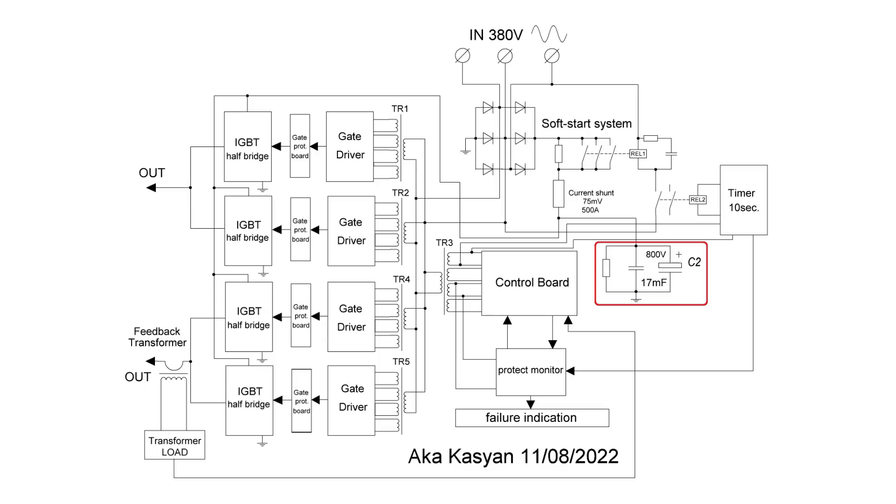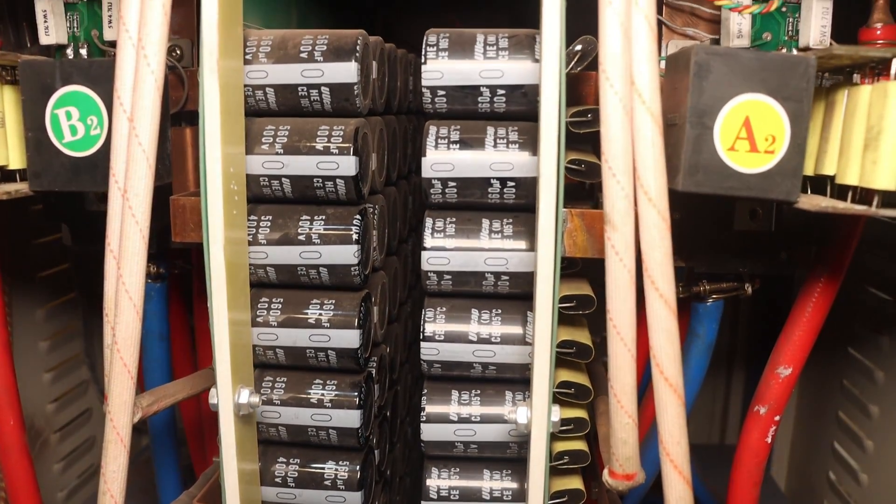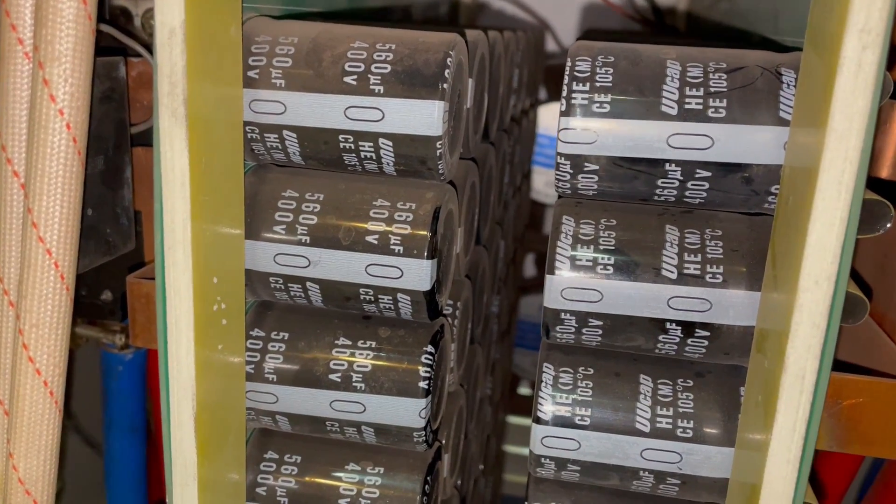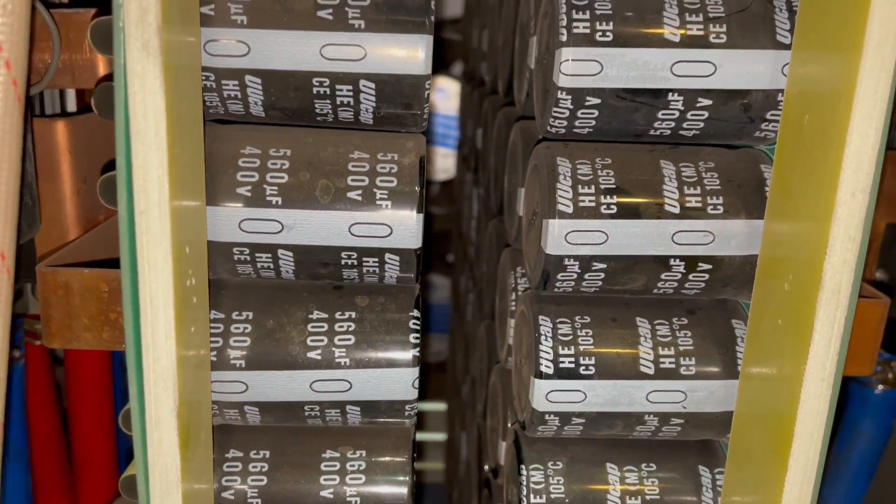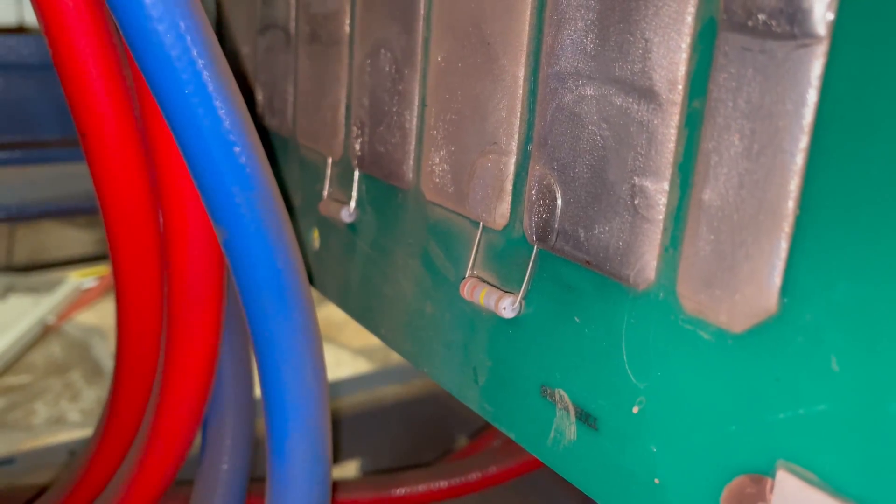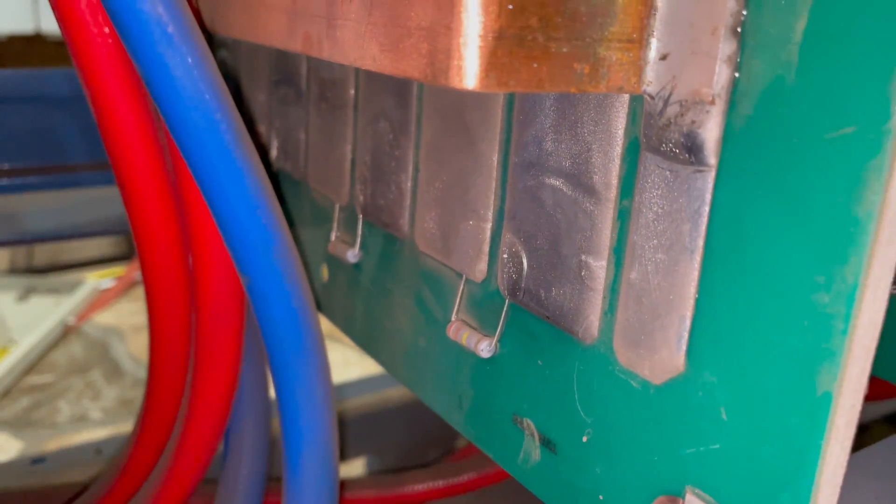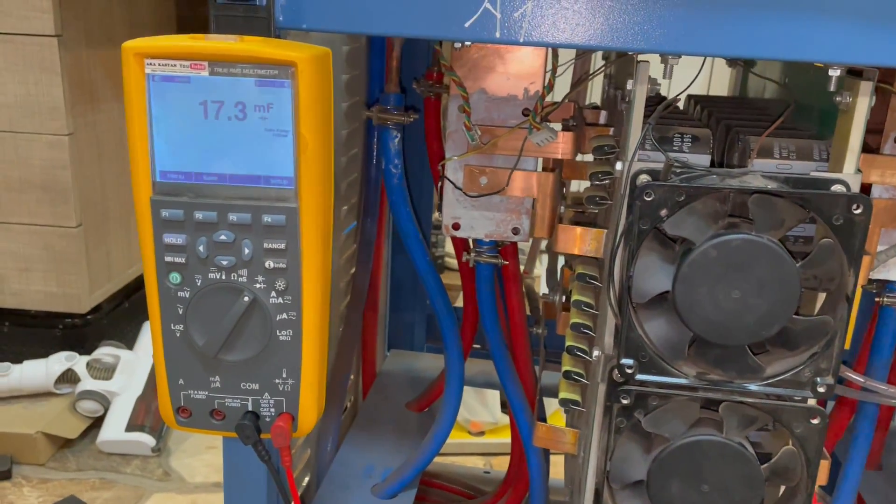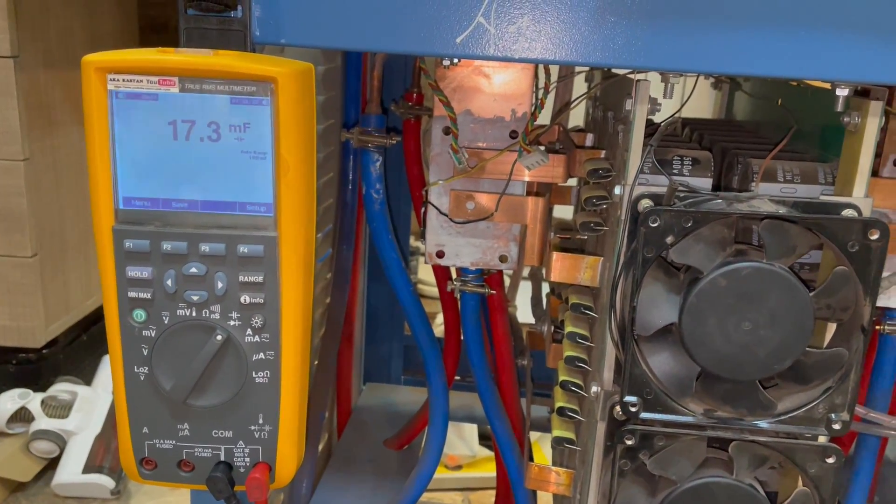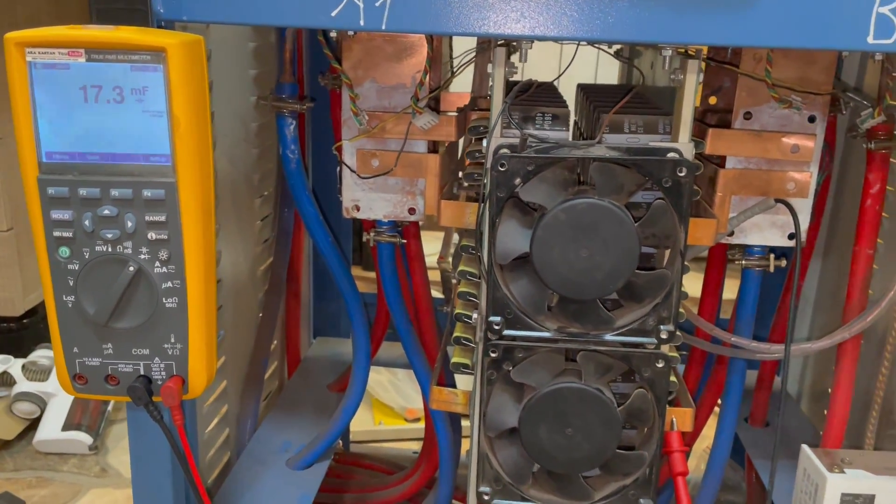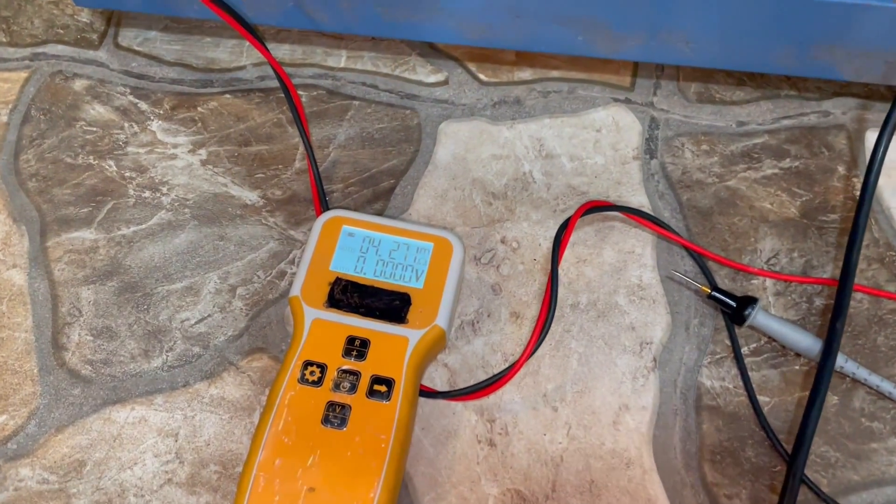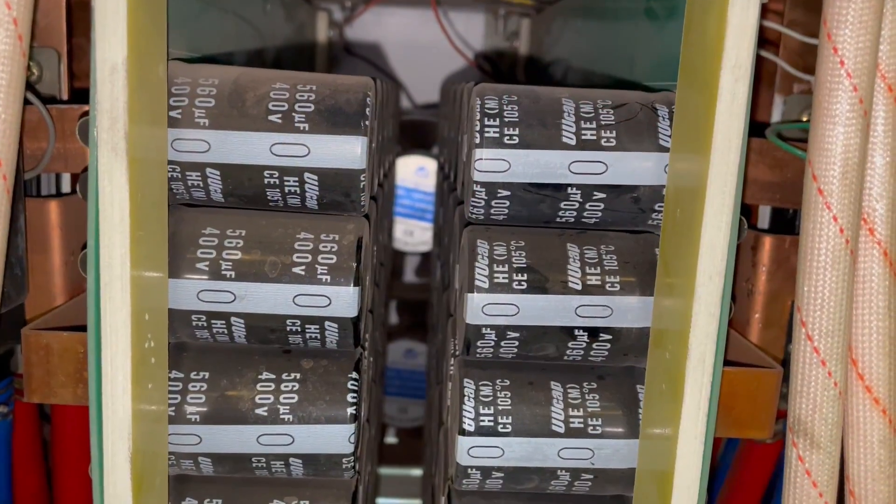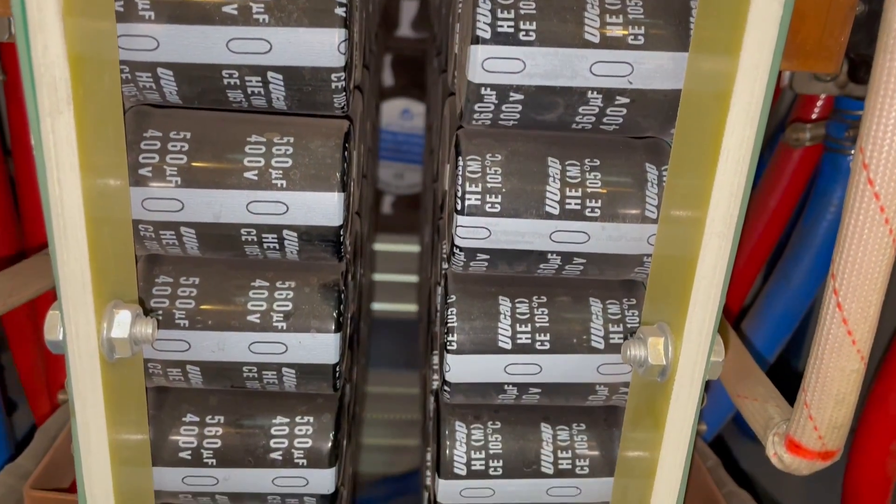Next is a power capacitor bank to smooth out power ripples. It's assembled on banks of 400 volts, 560 microfarads. The total voltage of the bank is 800 volts. The electrolytes are shunted with film capacitors. There are a bunch of discharge balancing resistors. The capacitance was measured and it amounted to an impressive 17,000 microfarads. The internal resistance is quite low and is a bit more than 4 milliohms. No visual damage was found. All capacitors are normal.